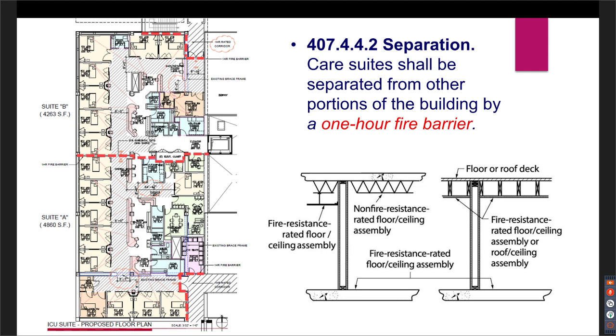So you heard me say fire partition before. In 1 hour, there are different wall types. Please make sure to use the appropriate wall type, because how those openings are protected and penetrations are protected, ducts, etc., have different requirements for different wall types, even if they're both 1 hour. So for suites, they need a 1-hour fire barrier surrounding that suite. And you can see the image to the left there. You've got 2 suites shown. That red dashed line is indicating the 1-hour fire barrier between the suites and then around the suites.